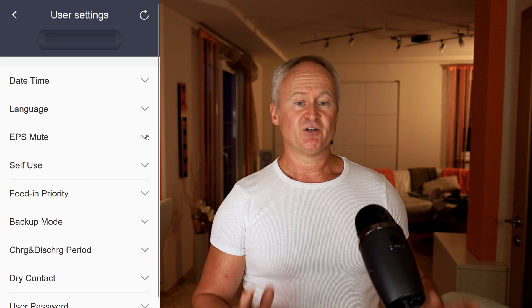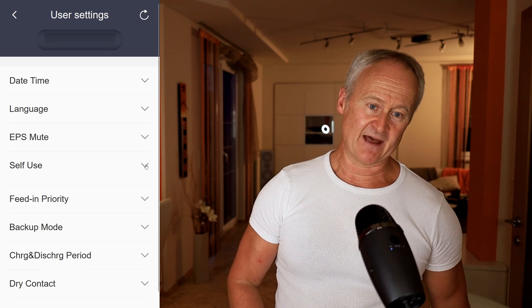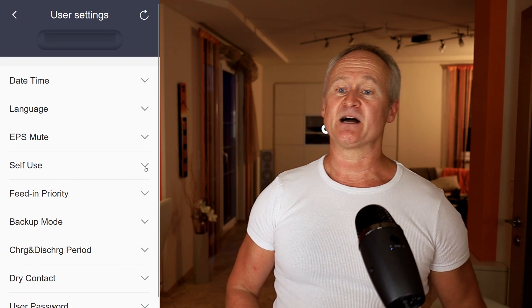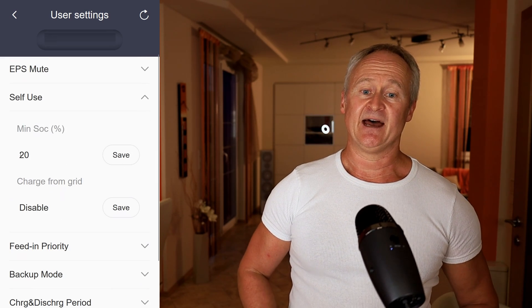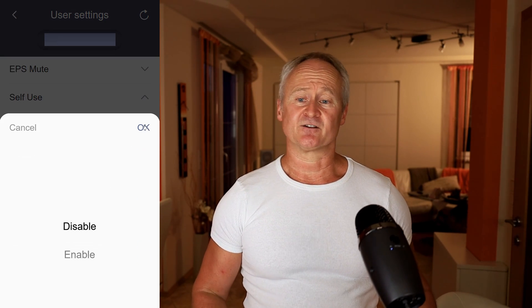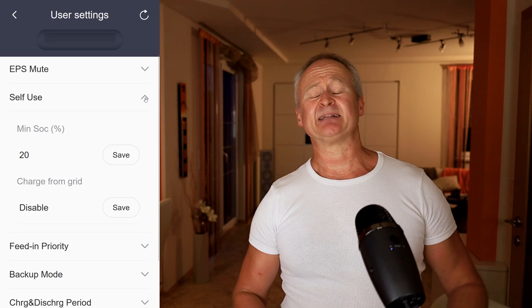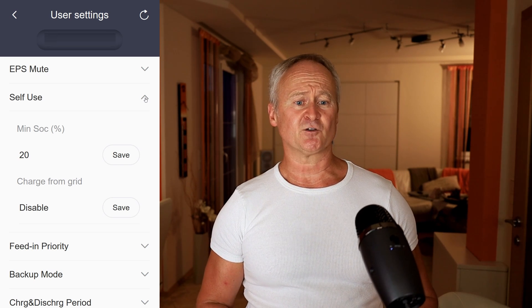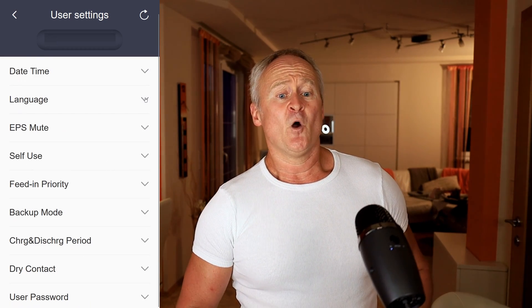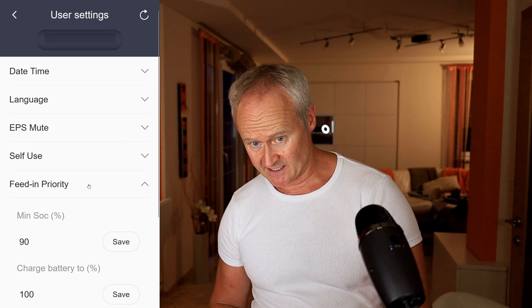In the following menu items, we can adjust the parameters of each work mode. Currently, we have set the operation mode to self-use. Here we can define how much we allow the discharge of the battery and whether we want to charge the battery from the grid or not. Under normal circumstances, we don't charge the battery from the grid, except in case of an anticipated blackout or when there is free electricity due to dynamic electricity tariffs. We have similar settings for the operation modes feed-in priority and backup mode.